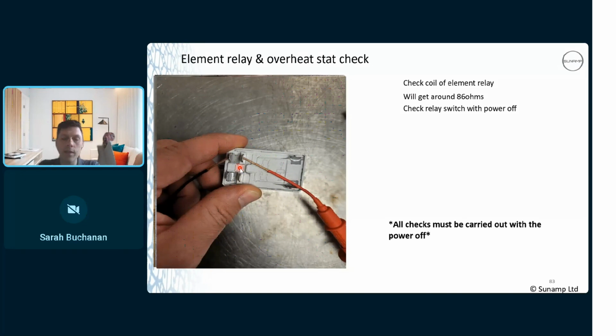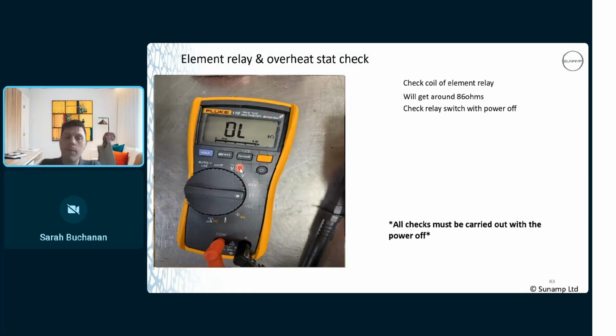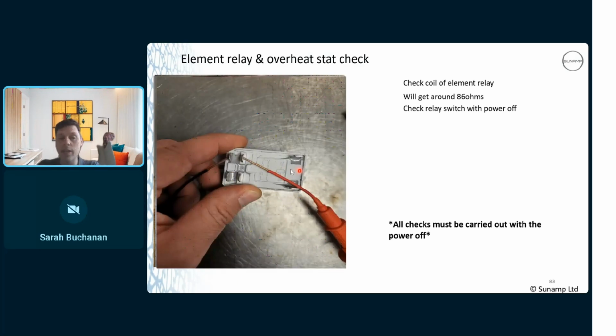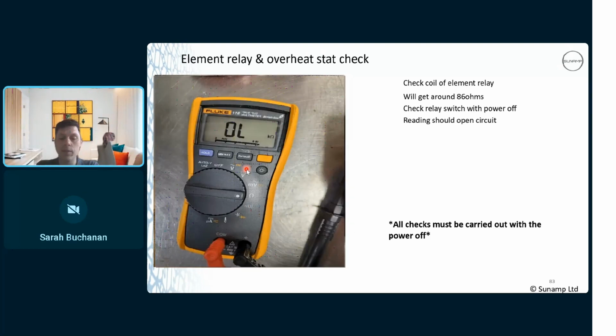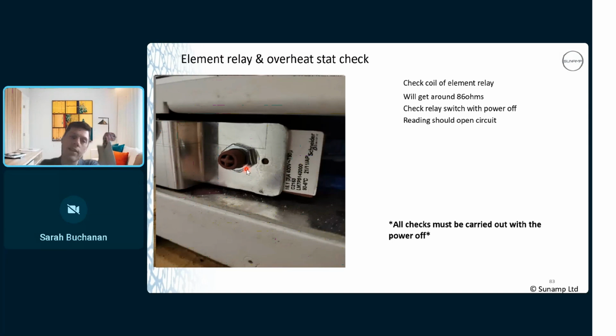So you should get open circuit with that. But you can also get a form of resistance going through it, and that can sometimes be enough to allow the flow of electricity. It's better to do this check after the relay's been energized for a while, because that can be when the relay contactor can stick, and that's the best time to check it. If it's cold, it will more than likely reset back to open again. That's your overheat stat there. So there's your temperature range: it trips at 96 degrees, and then it'll reset at 90.